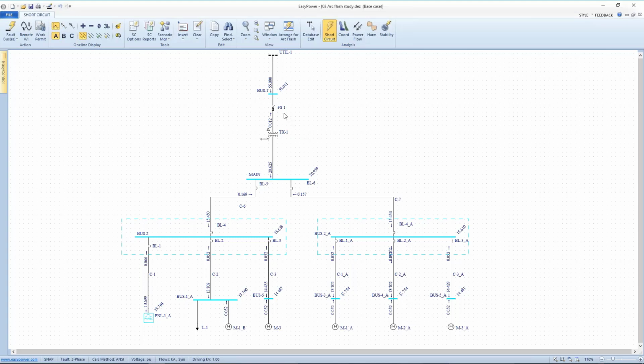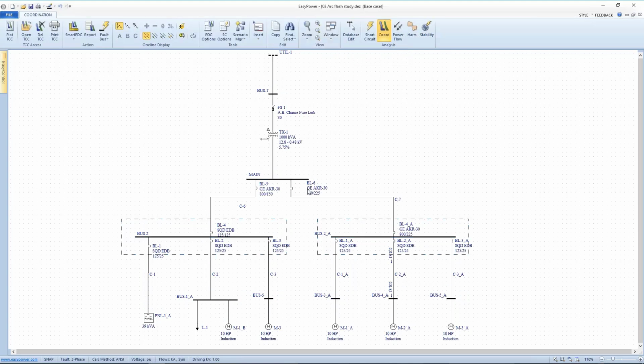Now, the next step in the process is more often than not what's referred to as coordination. So at least checking the coordination of the breakers. And what's meant by coordination: if I have a remote fault, let's say on this 10 horsepower motor, will my breaker system, the scheme that I have set up for my protective devices, eliminate that fault without dragging down the rest of the system? That process is called selective coordination, and in the vernacular of arc flash, the need to reduce incident energy actually contradicts the need for doing selective coordination.